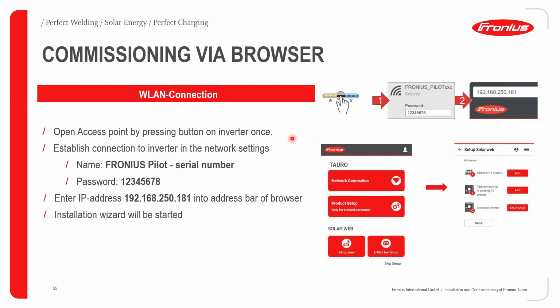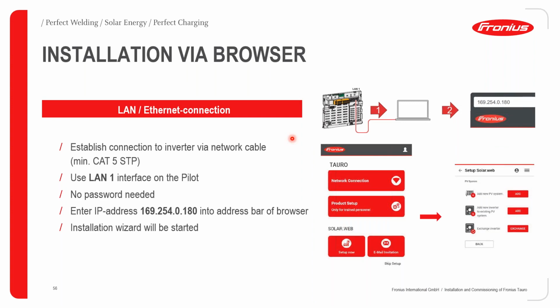Then another way you can do this is via using LAN or the Ethernet port or connection procedure. With this, you'd have to establish, of course, connection to the inverter. But in this case, you can use your network cable. We recommend a minimum of Cat5 cable. So Cat5 and above would do. And we also recommend that you use the LAN 1 interface port on the pilot, as indicated or shown here in this illustration. So once that is done, you don't need any password.